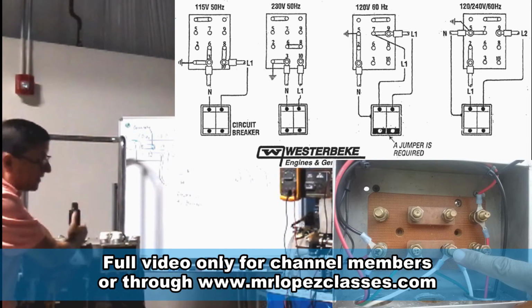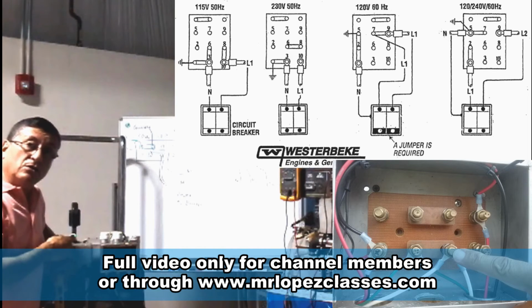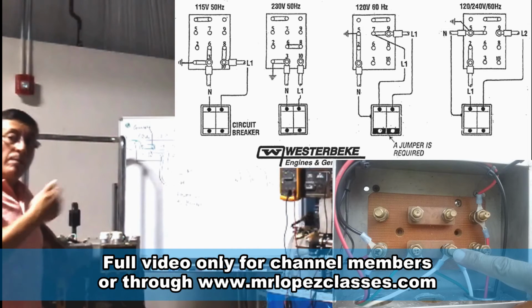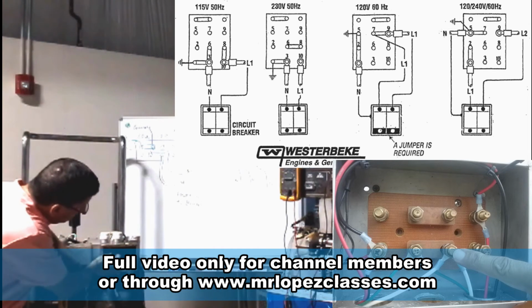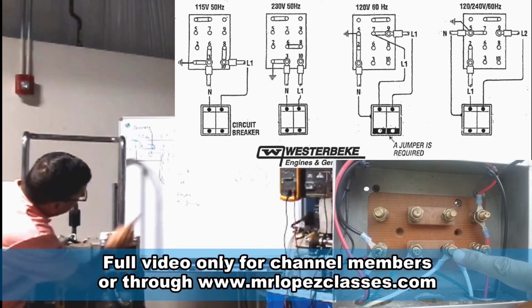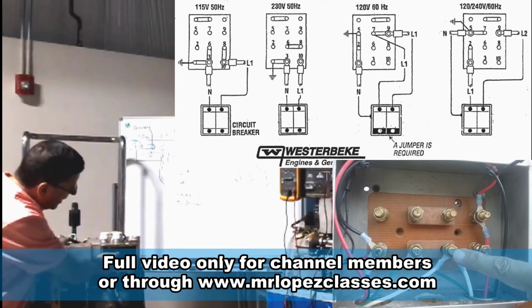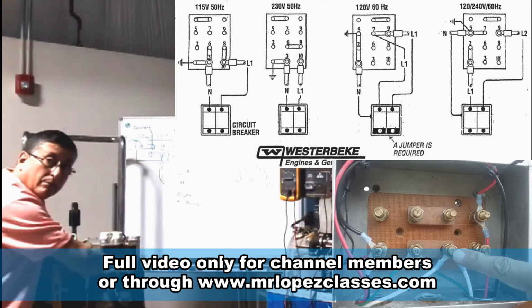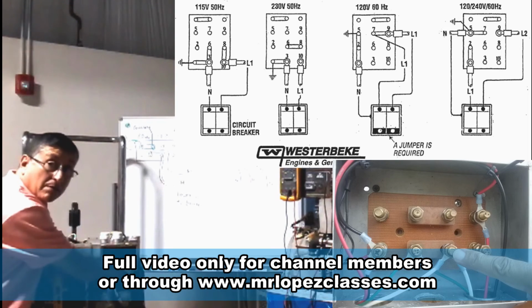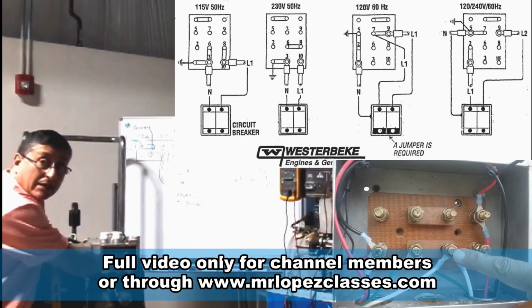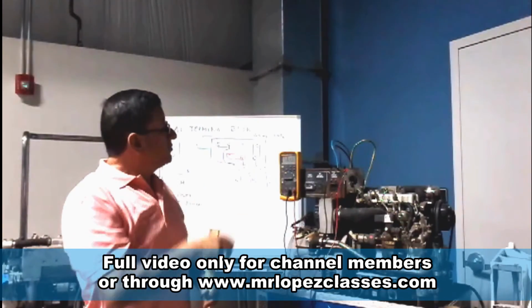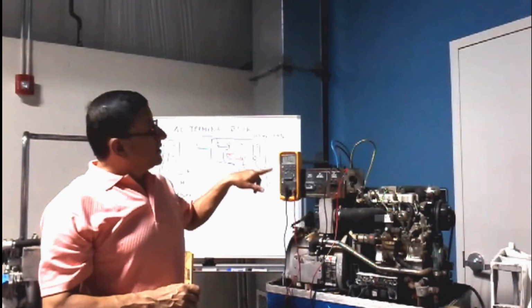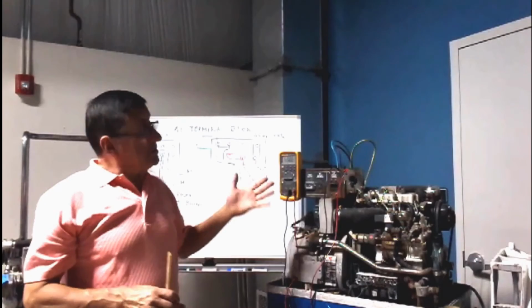For example, at this moment, this generator is a European generator. I want to convert the generator into an American generator. Okay, I move the terminals according to the new configuration, and now I tighten properly. Not too much torque because this is bakelite, like a plastic. You verify with full load on the breaker on the panel that the frequency stays at 60 Hz. My generator is converted.